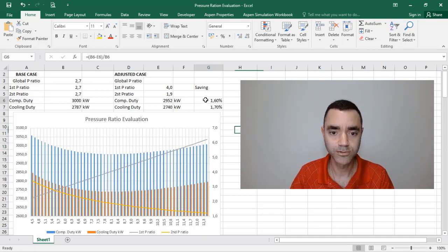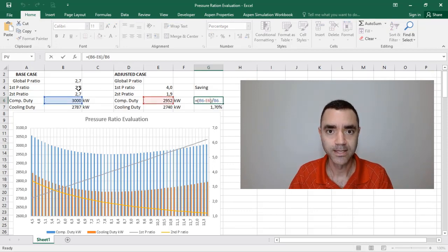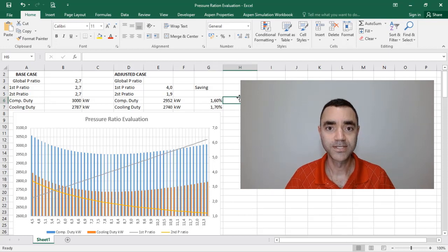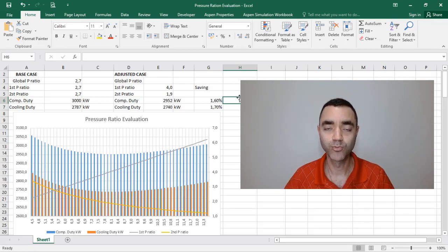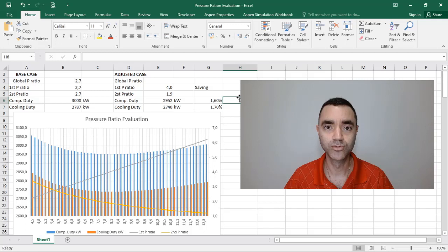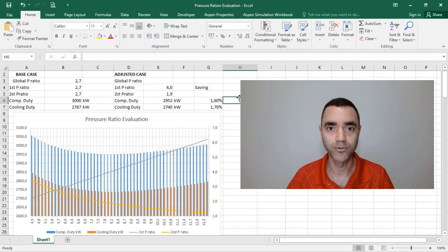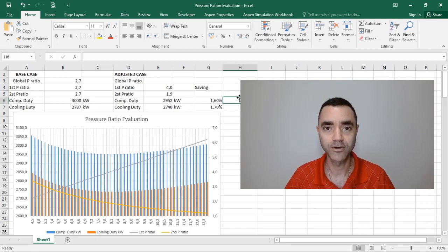This means that instead of using equal pressure ratios for both stages, it makes much more sense in terms of energy to have differentiated pressure ratios. I calculated the savings in terms of compressor power and cooling power. To quantify in monetary terms, you need to know the cost of electricity in your region. The higher the electricity cost, the more beneficial this optimized arrangement will be. If electricity is very cheap, this kind of optimization may not justify the additional complexity.